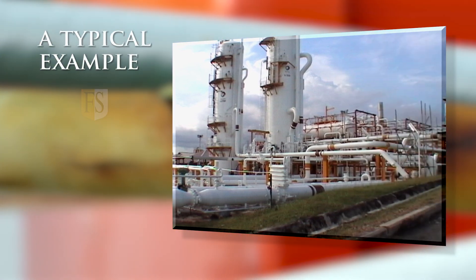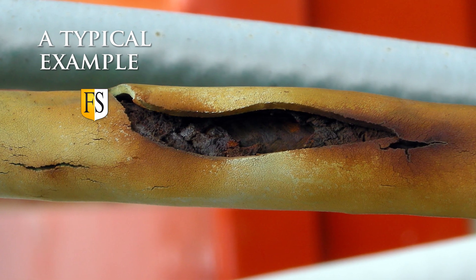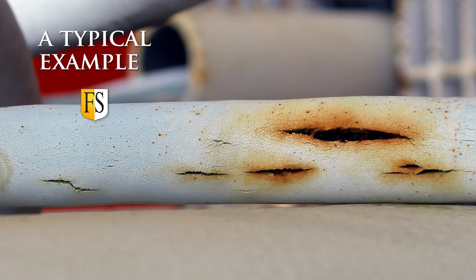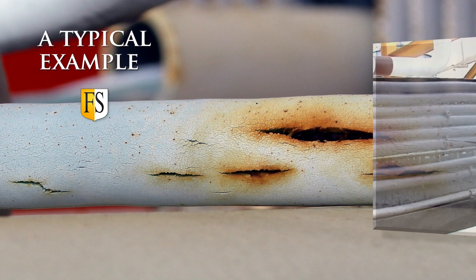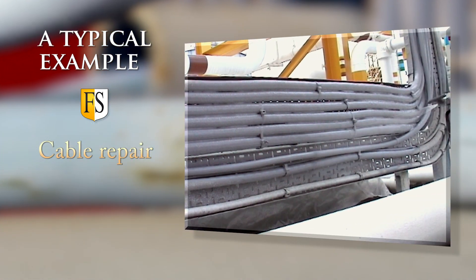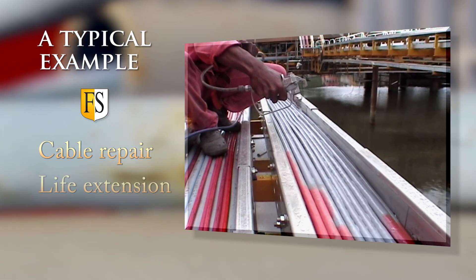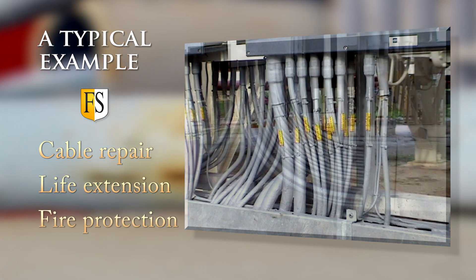A typical example is what Fire Security has done for the Senipah terminal in Indonesia for the oil company Total. The outer sheath of the cables was damaged, mainly by UV, and had a lot of cracks which led to short-circuiting and sometimes loss of production. Fire Security repaired all the cracks and coated the cables without any stop in the production. We have extended the lifetime of the cables and at the same time made the cables fire resistant.